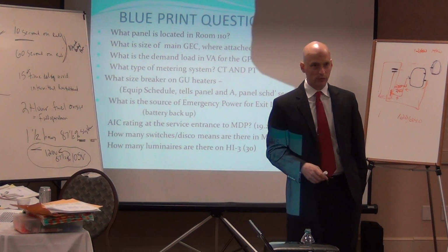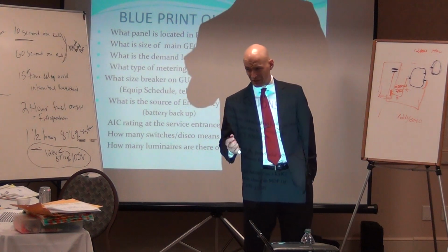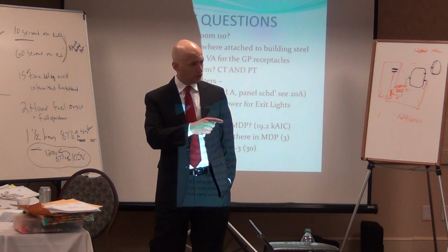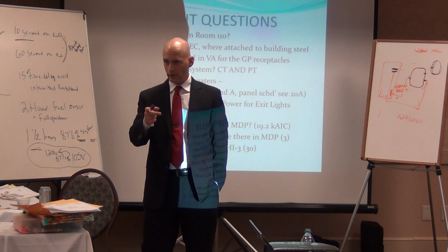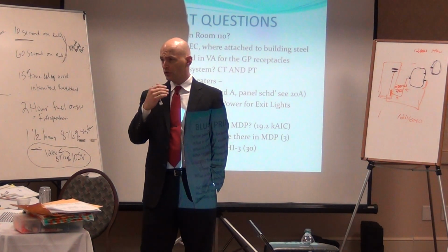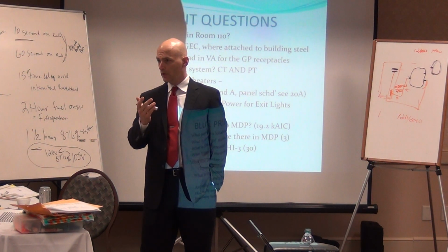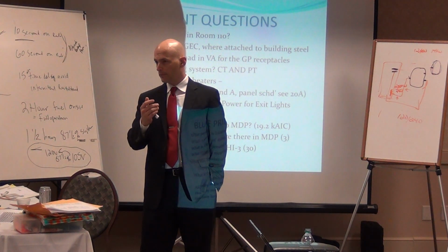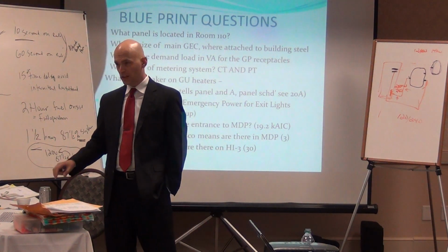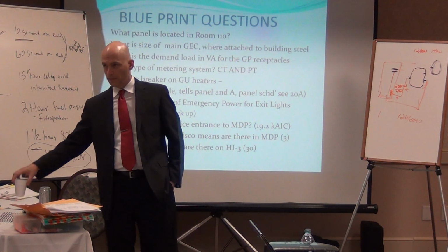And just as an example, to help clarify what we were talking about, the use of the water heaters. Somebody just brought that up like two or three days ago, so I've really heard it. I think you had it on yours, right? See, you should be using 120 volts as the value, and not 240. Well, both conductors combined on that conductor have a combined value of 240 volts. But that neutral's only carrying back 120 volts. Well, it's carrying back just the net imbalance between them, but you're right, it's a 120 volt rating.